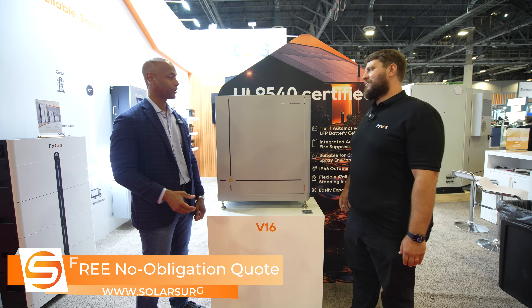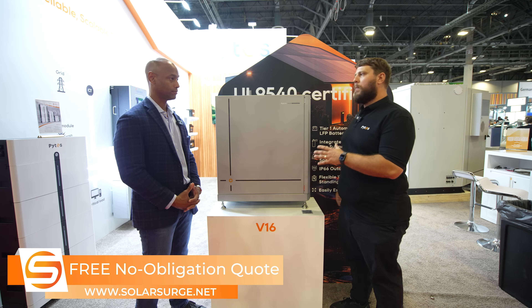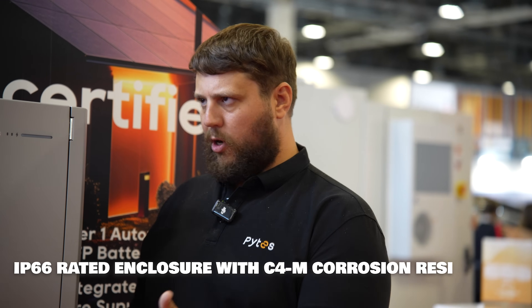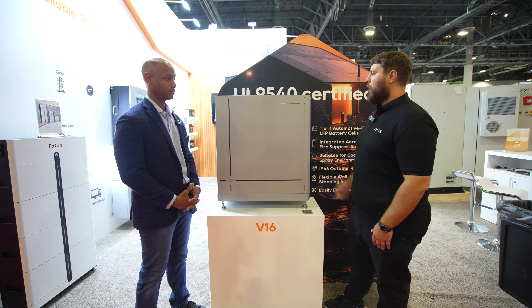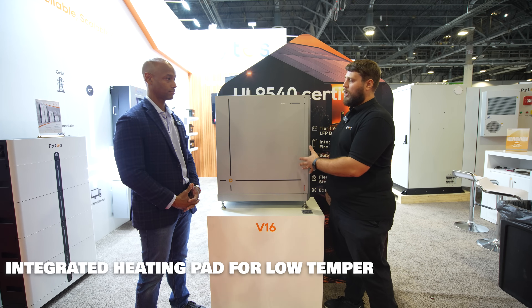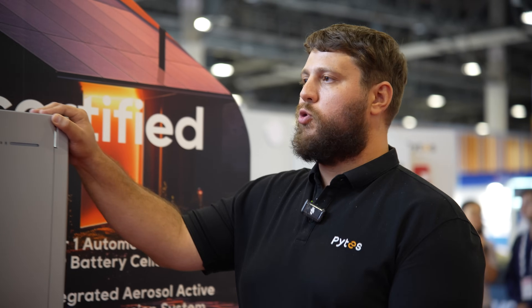Is there anything else the audience should know about the new Pytes V16 battery? We really went after engineering the most robust wall mount battery in the market. Additional features include internal corrosion resistance — the internal components are coated in a C4-M coating for corrosion resistance, as well as the outside. This is great for coastal and humid climates. Also, there is a heating pad built in, so for colder climates and outdoor installations, the heating pad allows these to be installed in cold and cool weather climates as well.